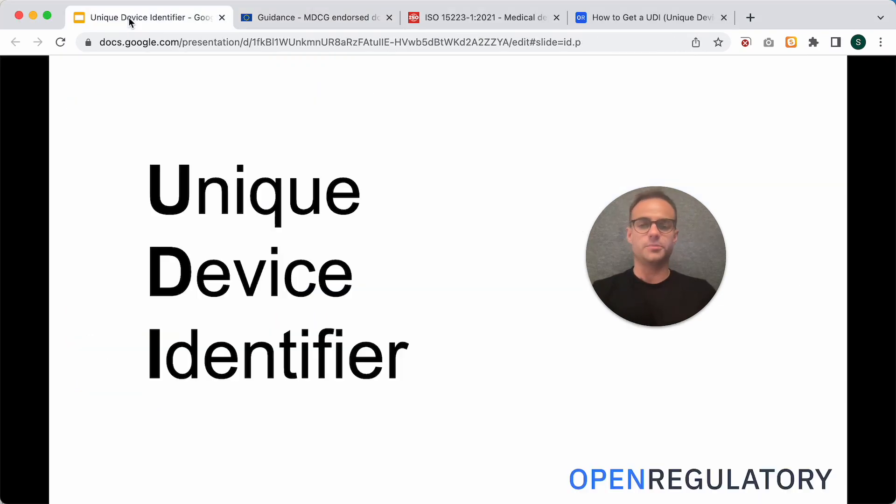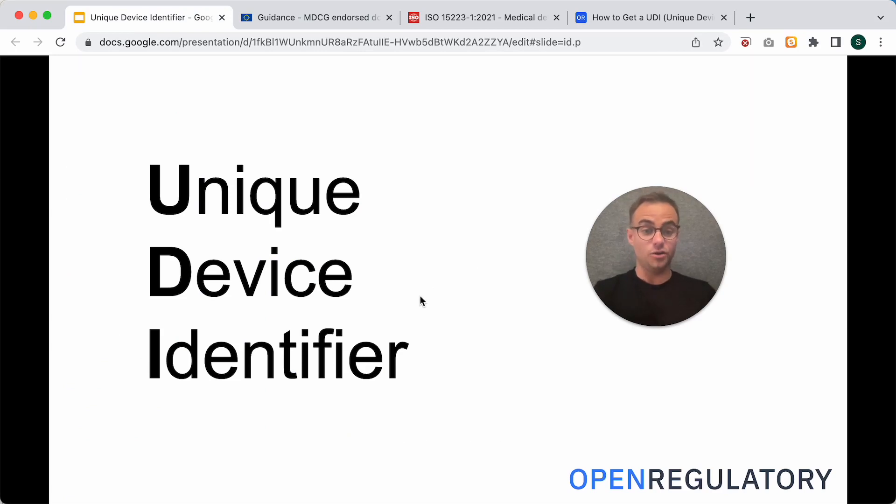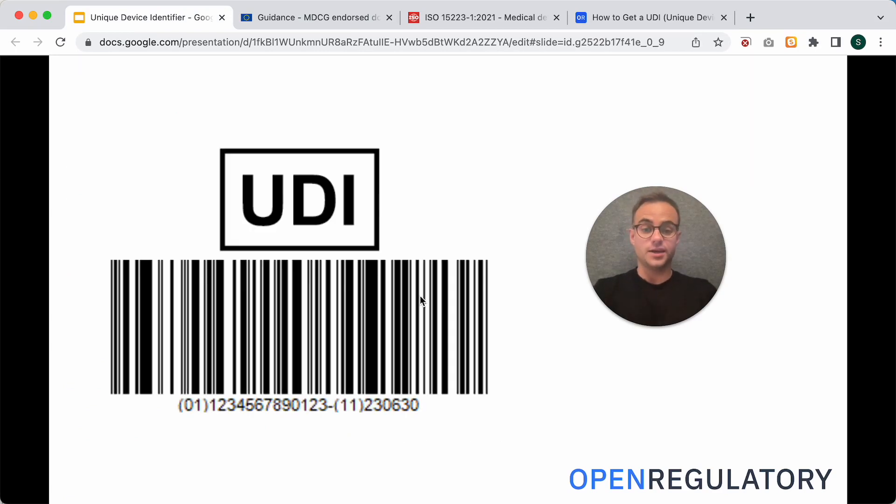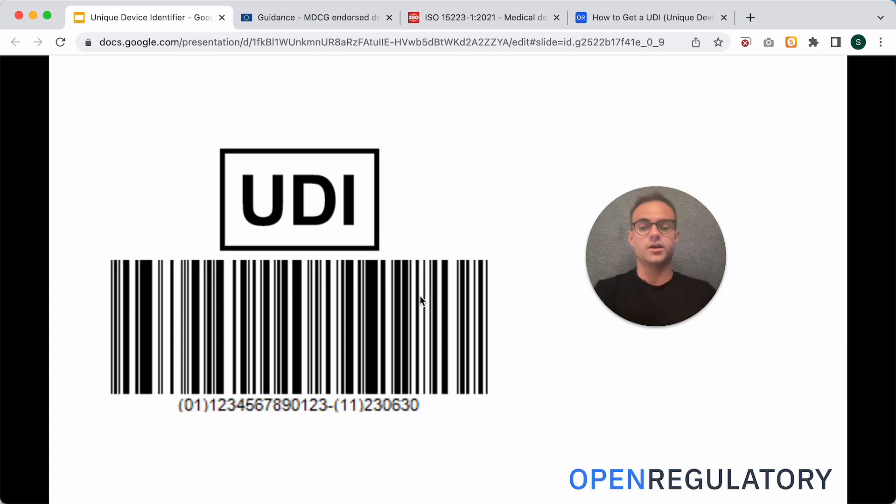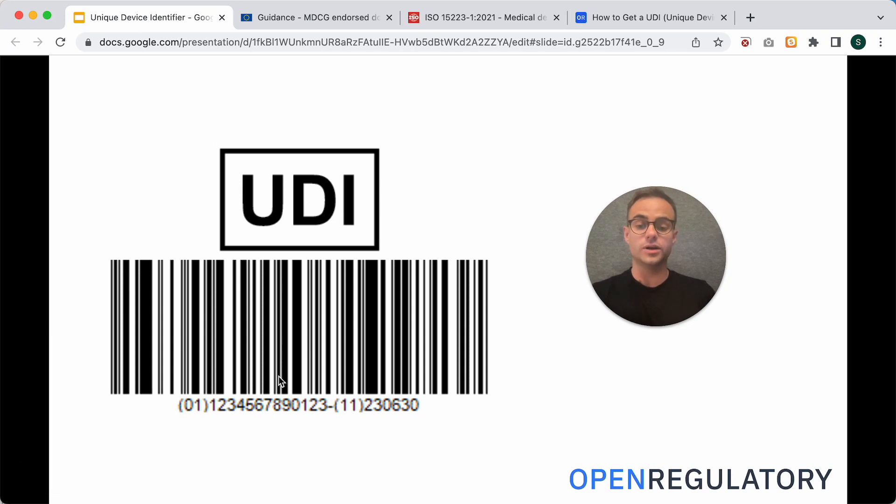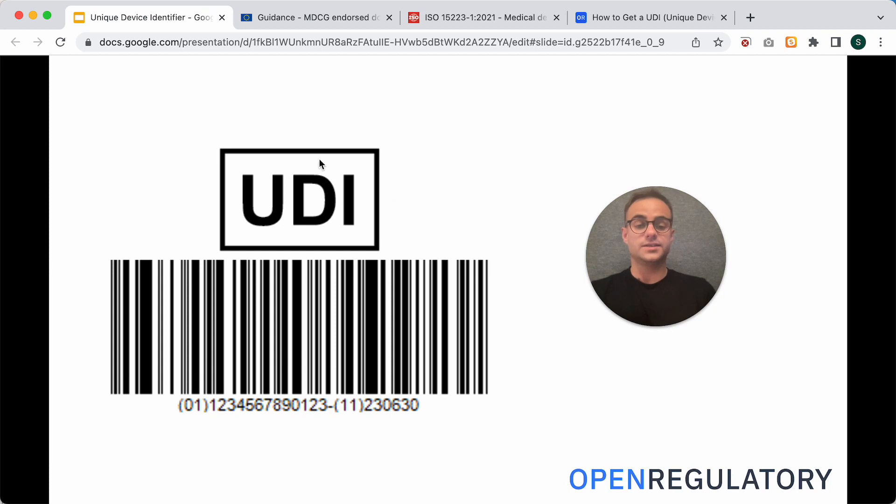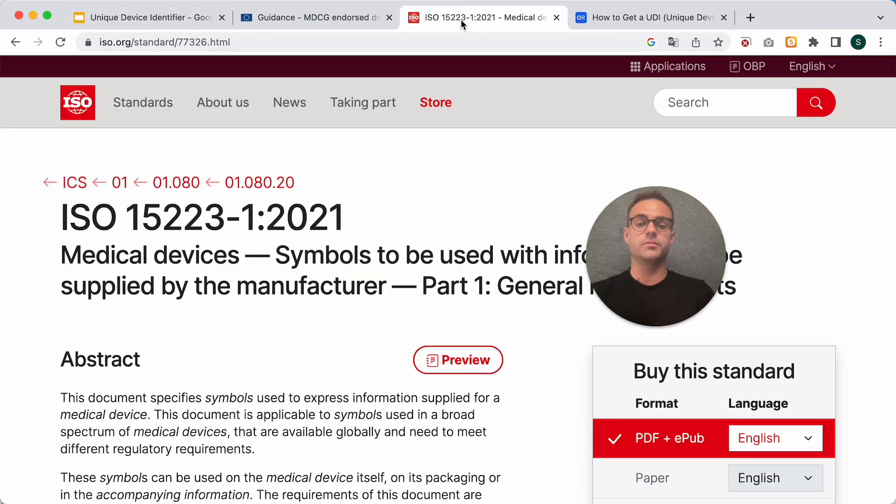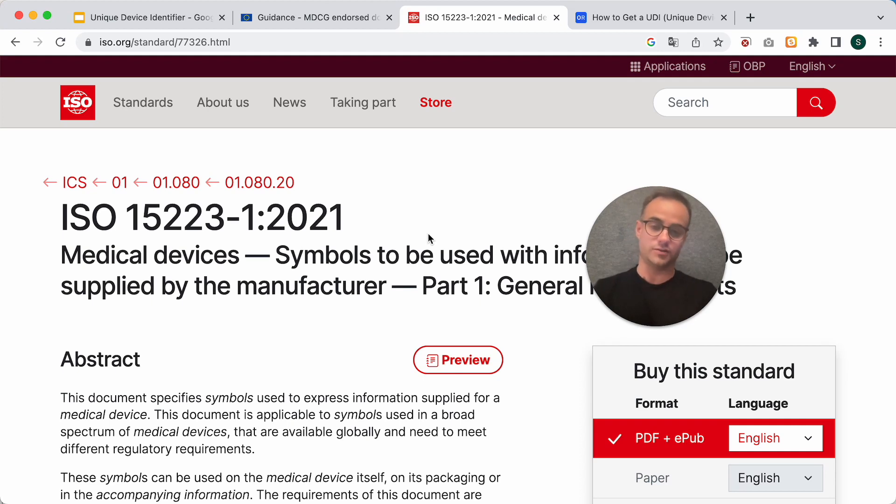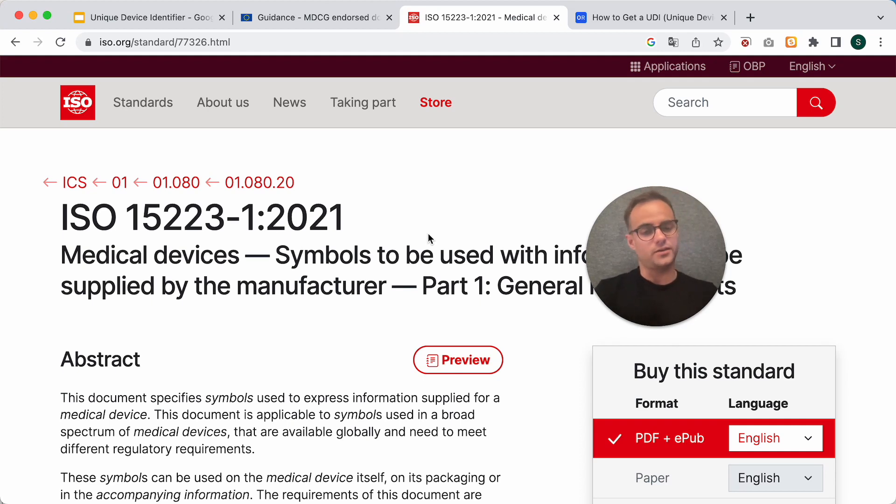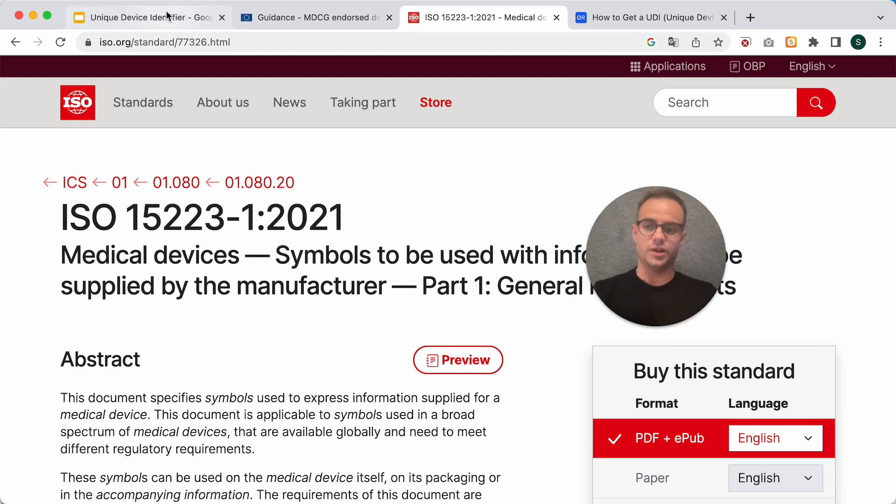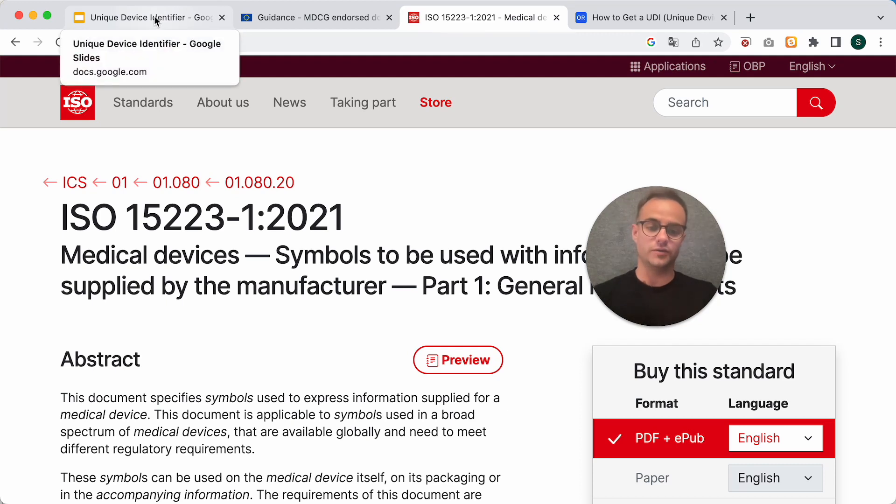But let's jump right into it. How does a UDI look? Here you can see how a UDI would look on a finished product. You have the UDI symbol, then the machine-readable UDI barcode, and the human-readable version of the UDI. This symbol is mandatory, and it comes from ISO 15223-1 from 2021, where you can also find other symbols, like the MD symbol and other stuff that's relevant for your medical device documentation.